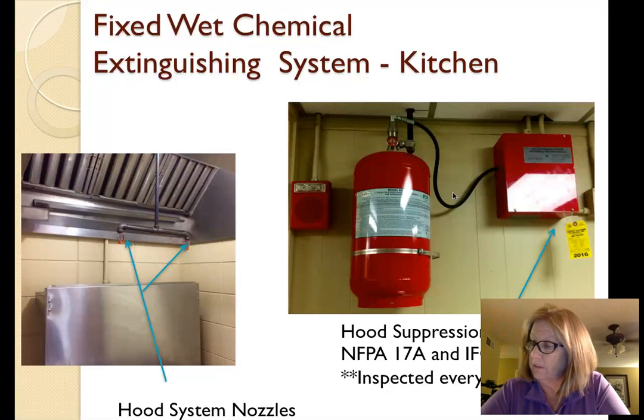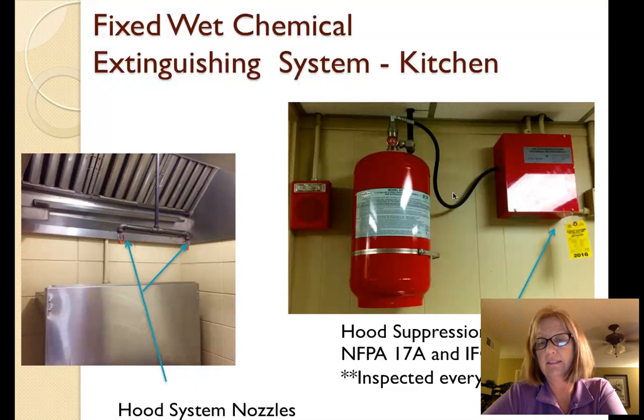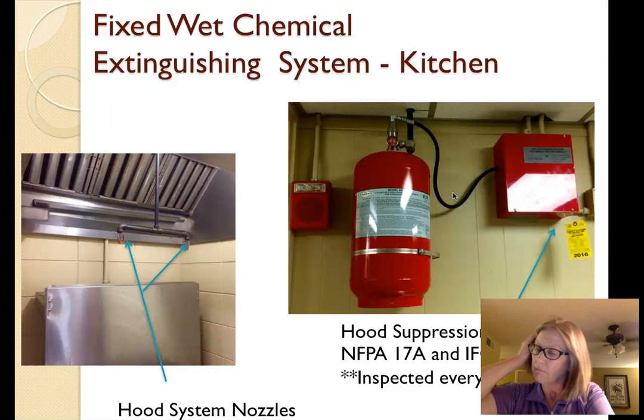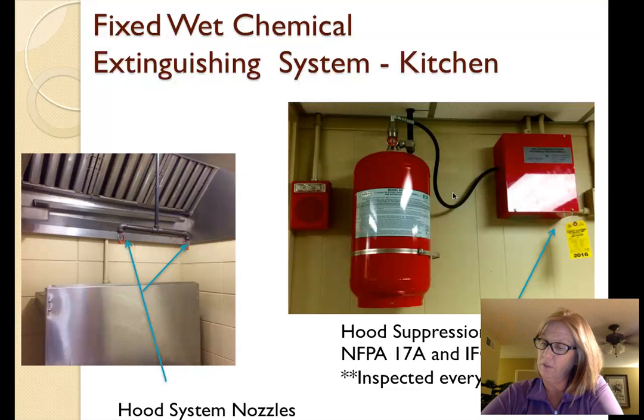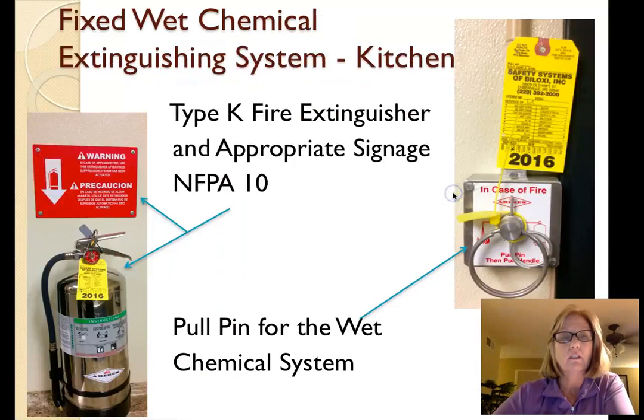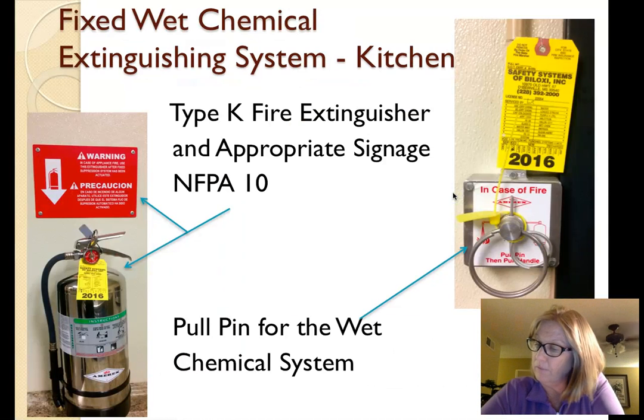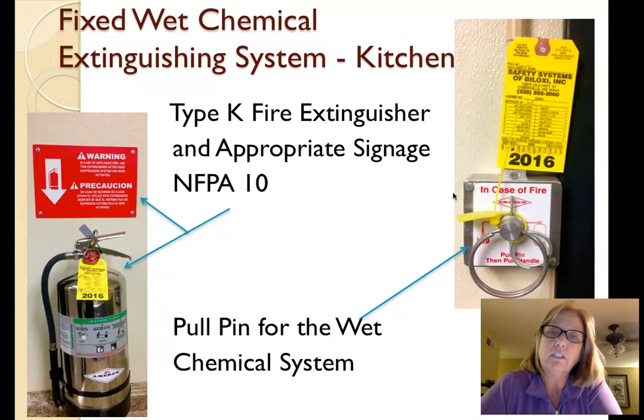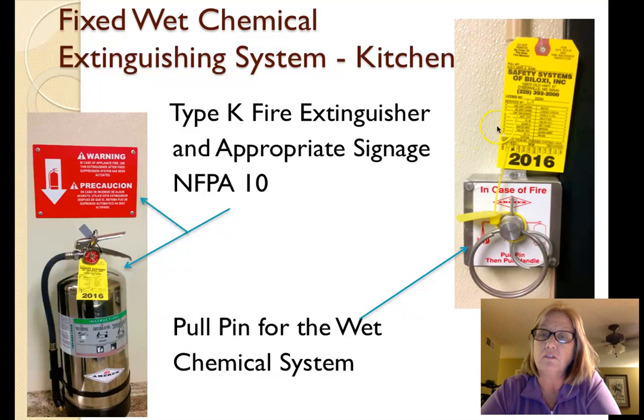From the entrance to the right, there was a kitchen that contained a hood suppression system as required by NFPA 17 and International Fire Code 904.5. The tag on the system was dated October of 2016, and per the NFPA 17A standard, the hood system has to be inspected every 6 months. We also saw a Type K fire extinguisher inside the kitchen area that had appropriate signage over the top according to NFPA 10. It also showed a pull pin for the wet chemical system on one side and also had an inspection tag there.